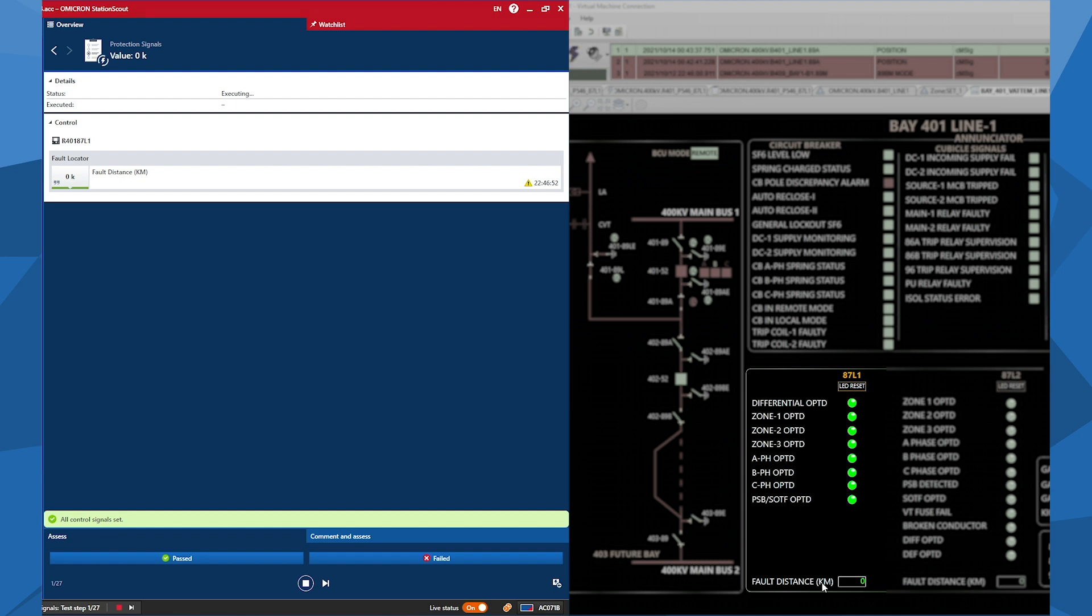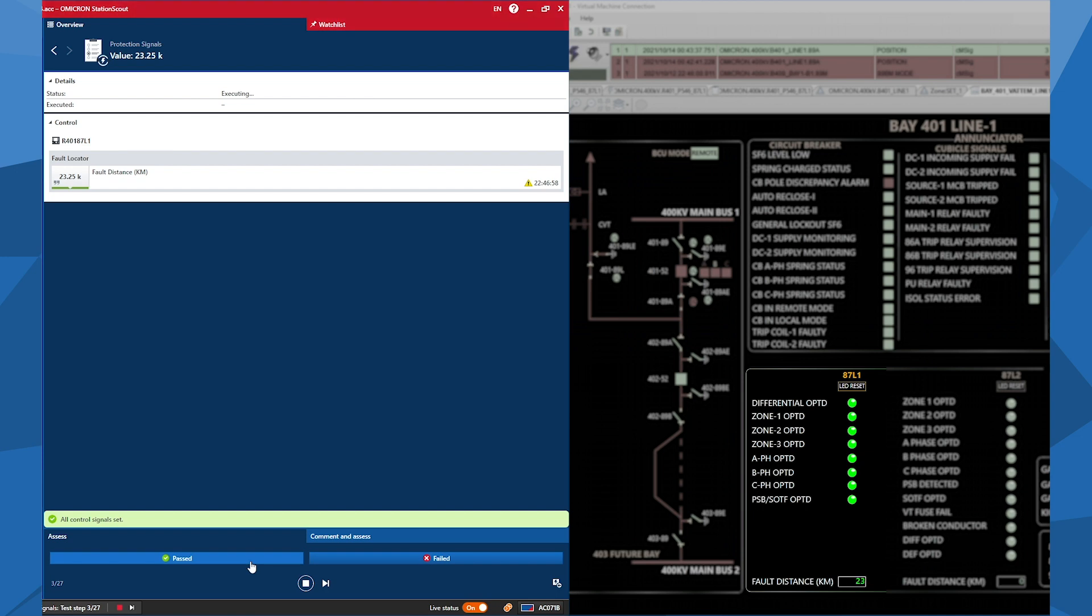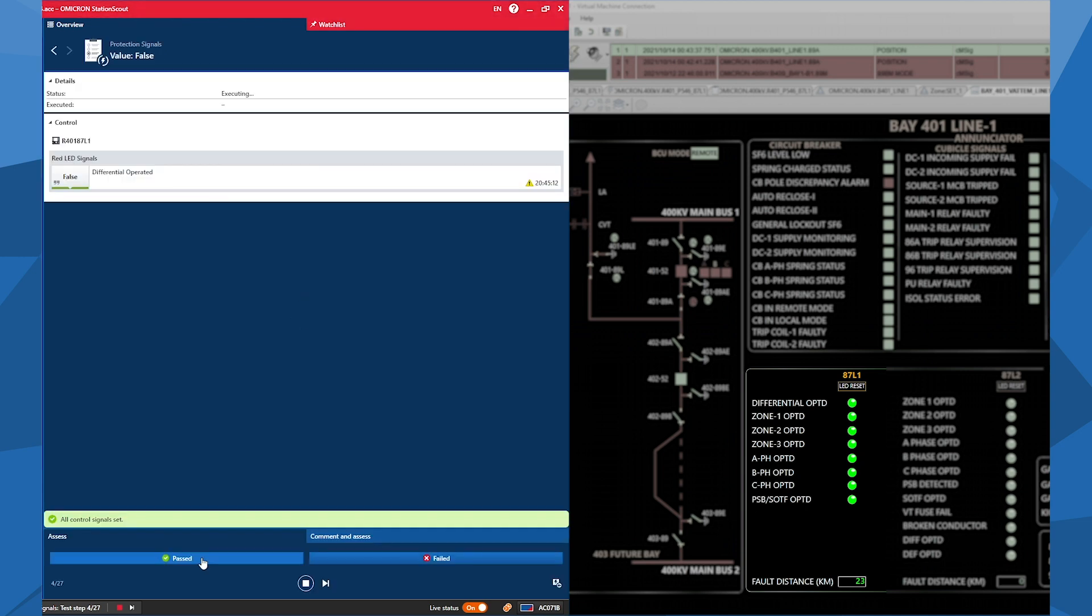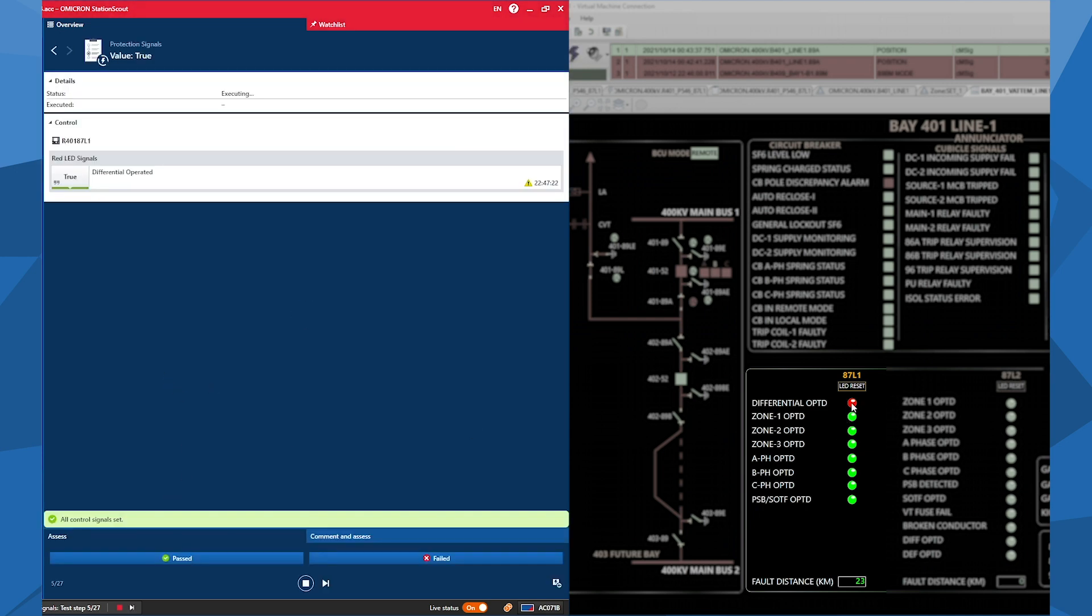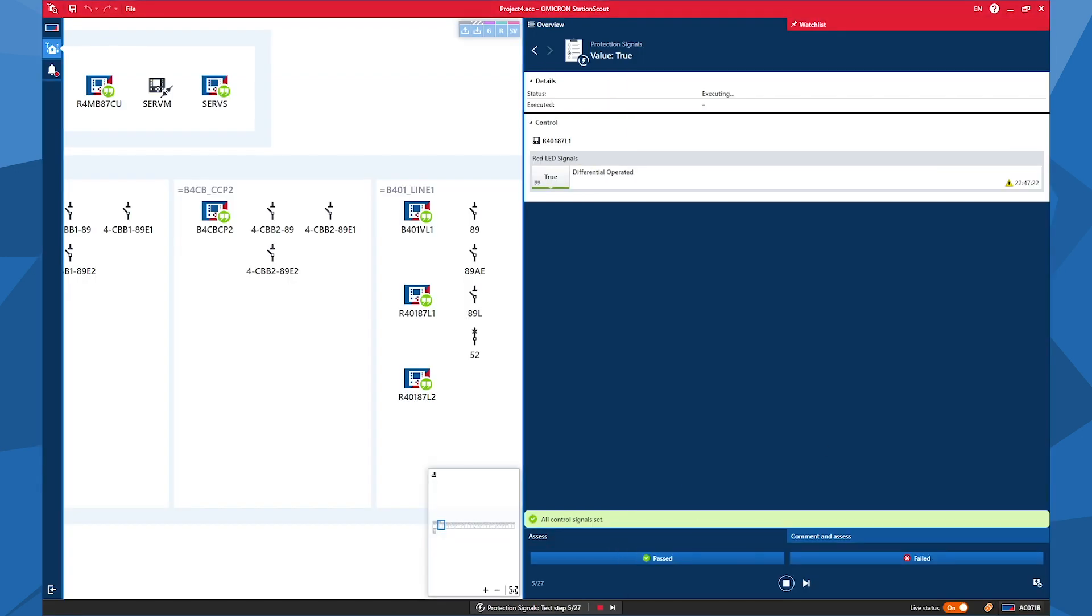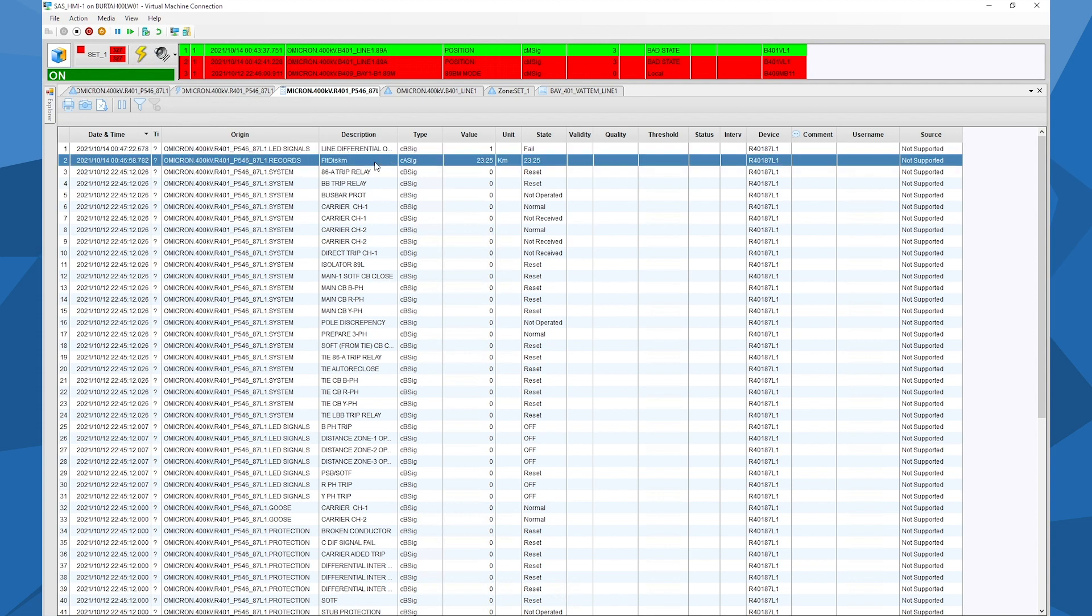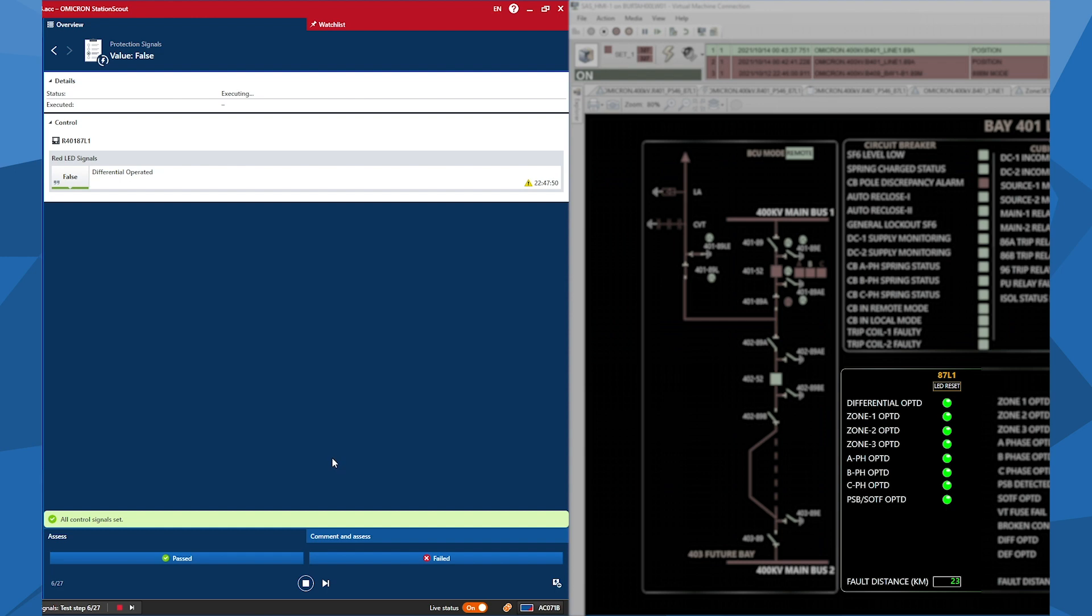And now we start the test with fault distance. Now it should be zero. Yes, that's true. Now it should be 100 kilometers. Now it should be 23.25. So now I catch that we don't have the, yeah, nothing more than the decimal values here. Okay, that's a finding for me. And now I have the differential operated as false. Now I expect to have it as true. Okay. So maybe we can also check in the line differential. So now it's working fault distance. Now we can see the event log. So we can take some notes on that, or we can move on. So now I see that differential operated LED is false. So this can move on like this.